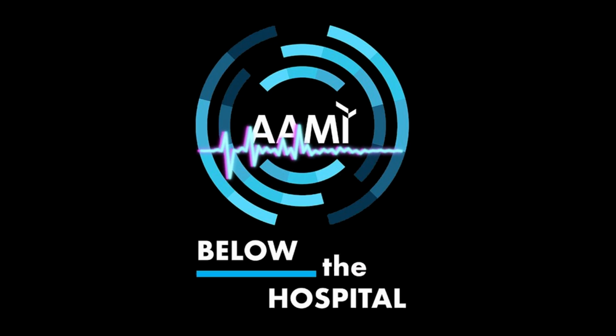Good. When it comes down to it, I'm convinced, and as I talk to other experts in the industry, I think we all agree, in most cases you could use radiation or ethylene oxide. And you notice I use the general term radiation instead of defaulting to gamma. Gamma, X-ray, E-beam, generally they're about the same as far as impact to product with any damage that might be occurring to the product. So when it comes to radiation versus ethylene oxide, which is the other significant method, about half or a little more than half of single-use healthcare products are sterilized with ethylene oxide. And it turns out in most cases, you could use EO versus some form of radiation.